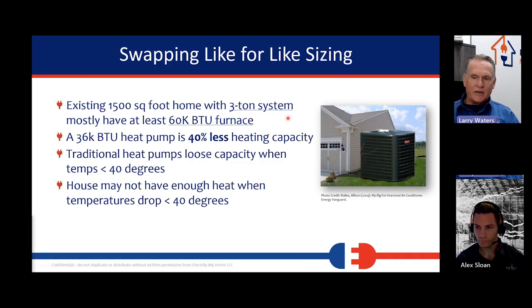Stop doing those. They have solutions so that you don't need to do that. And we don't need to put in something that's going to use more energy for the same solution. So if we have a system that cycles on and off, it's possible as it's getting really cold outside, this unit is not going to be able to keep up on the next cycle if the outdoor temperature drops below 40 degrees. It might not have enough capacity to warm the house up again.